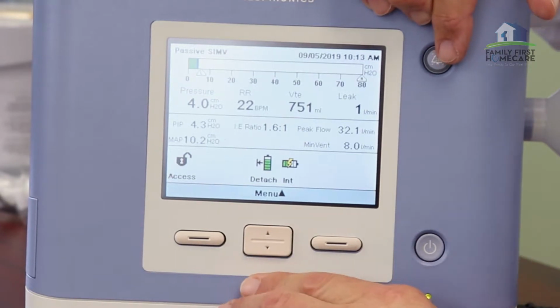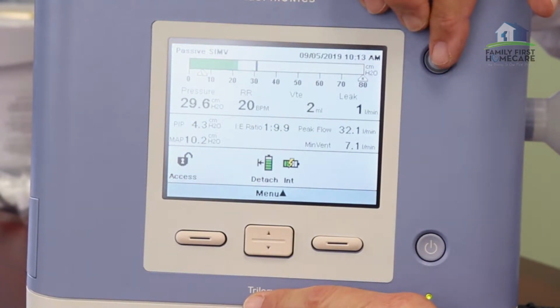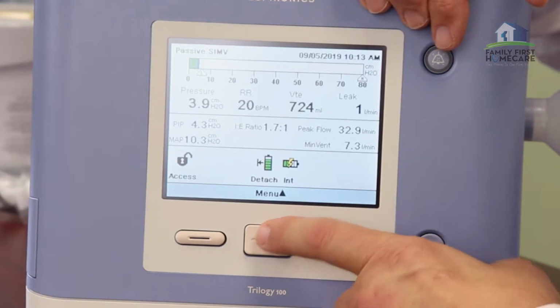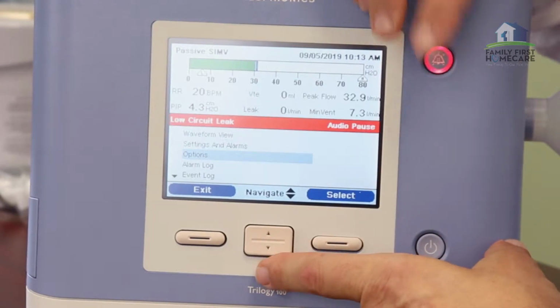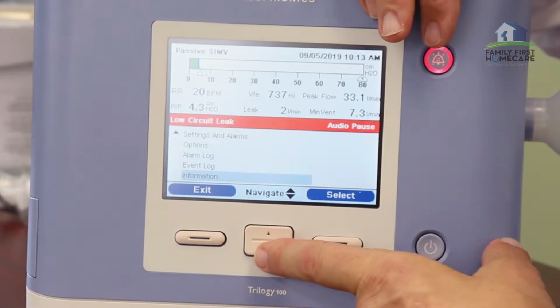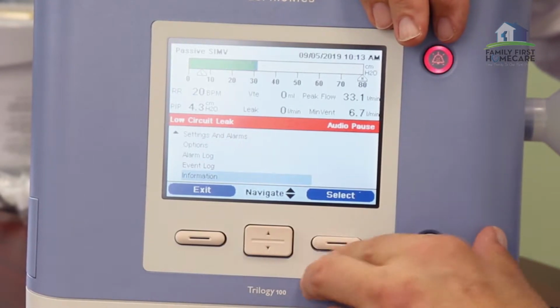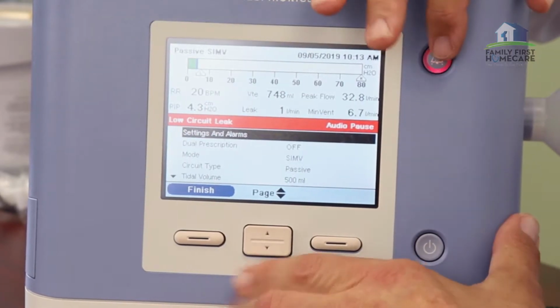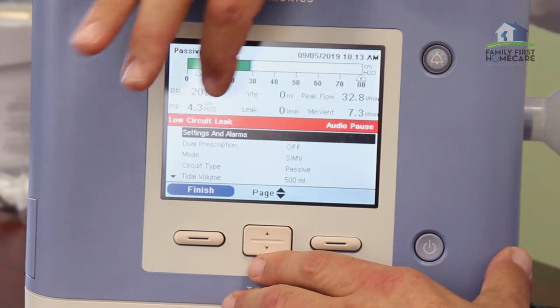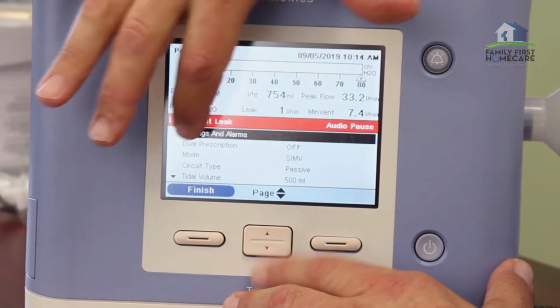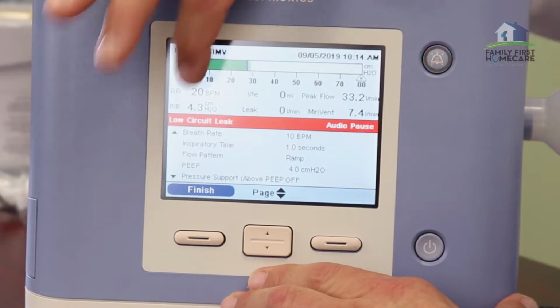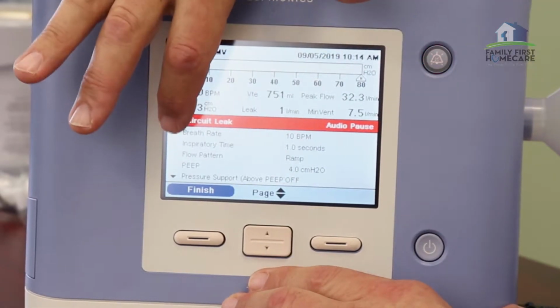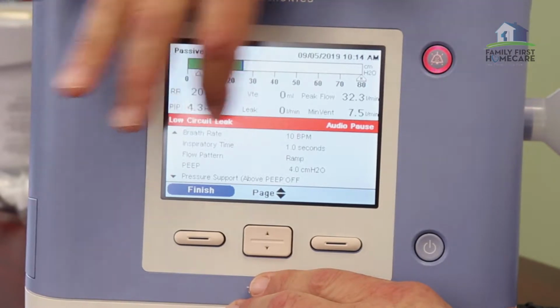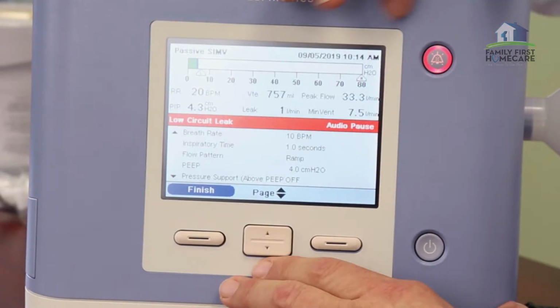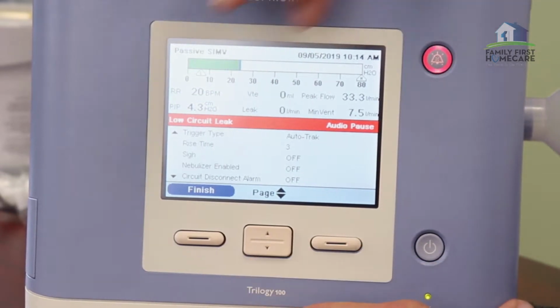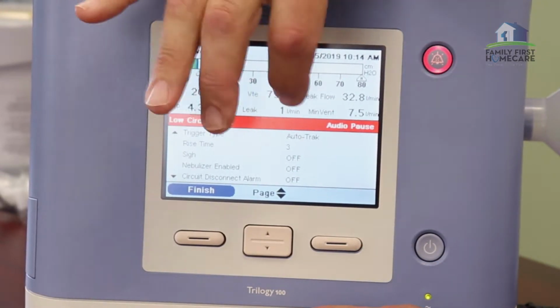What you're going to see is how to get to the doctor's orders. You want to know what the settings are. So on the top button, just flip up and go down all the way to Settings and Alarms. You would click on Settings and Alarms, and you will see right in line as you go down all of your settings. So you'll see that it is an SIMV, circuit type passive, tidal volume 500, breath rate 10, inspiratory time 1, flow pattern ramp, PEEP 4, pressure support is off, trigger type auto-trak, rise time 3.